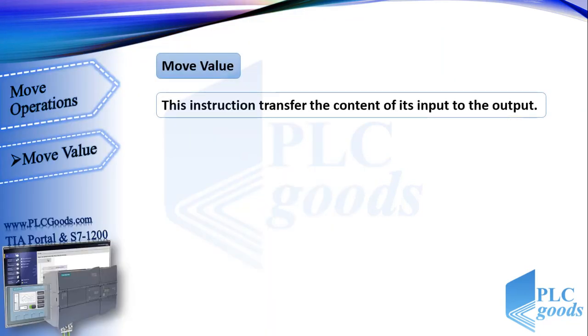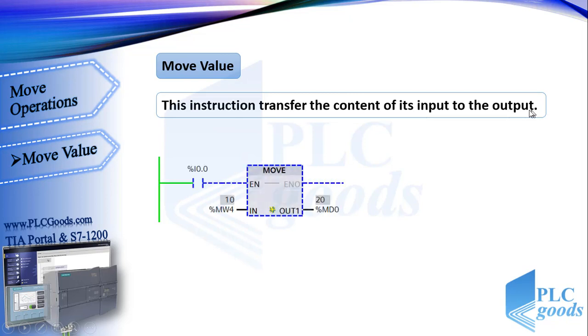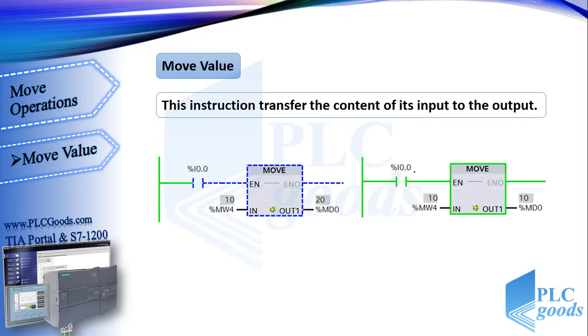The first instruction is move value. This instruction transfers the content of its input to the output. This is its ladder symbol. Now the value of MW4 is 10 and MD0 is 20. When I activate this instruction with this contact, the value at its input will copy to the output.